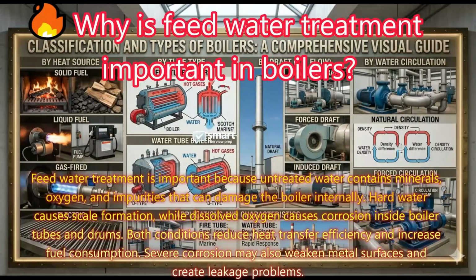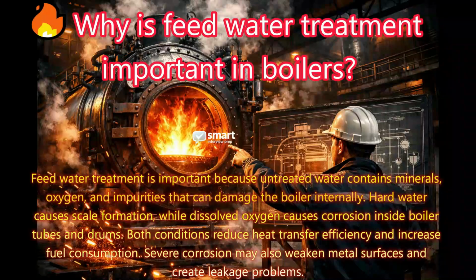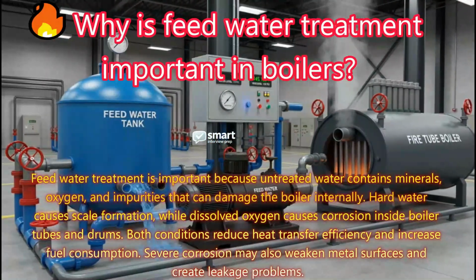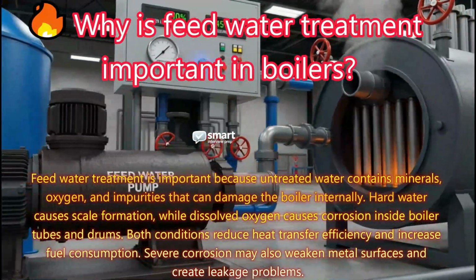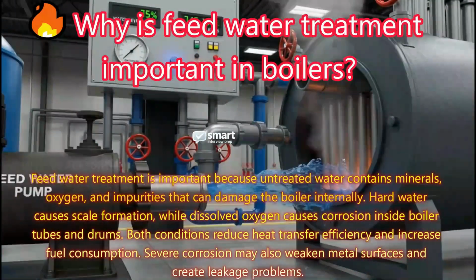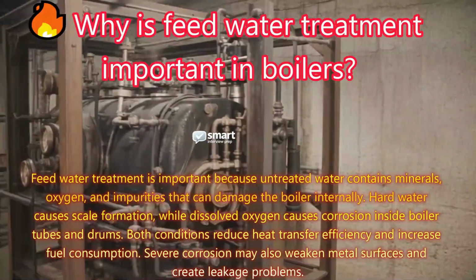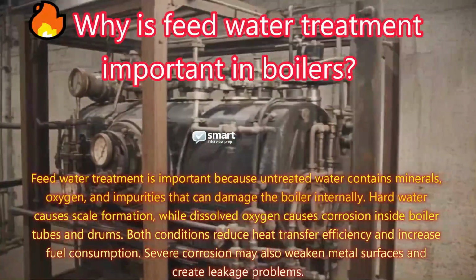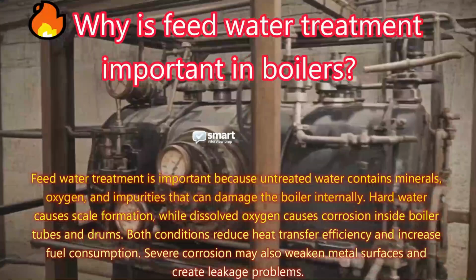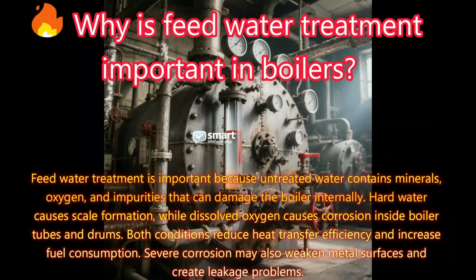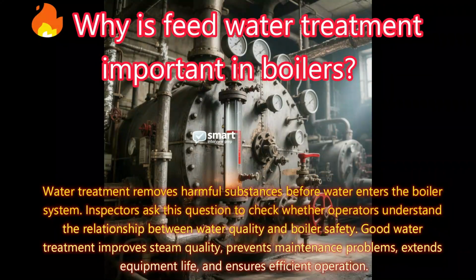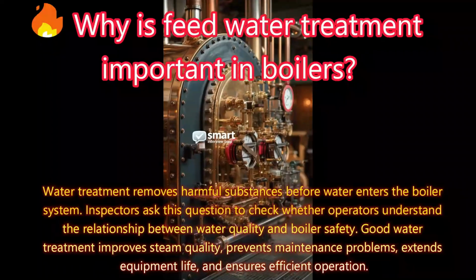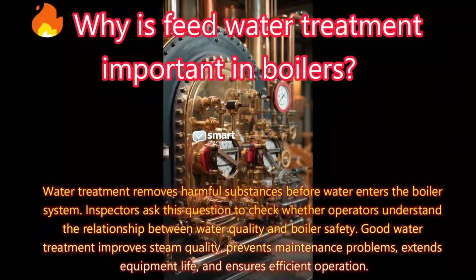Answer: feed water treatment is important because untreated water contains minerals, oxygen, and impurities that can damage the boiler internally. Hard water causes scale formation, while dissolved oxygen causes corrosion inside boiler tubes and drums. Both conditions reduce heat transfer efficiency and increase fuel consumption. Severe corrosion may also weaken metal surfaces and create leakage problems. Water treatment removes harmful substances before water enters the boiler system.